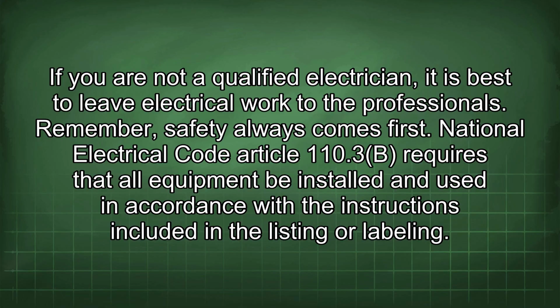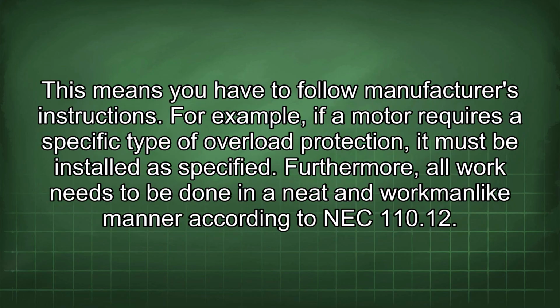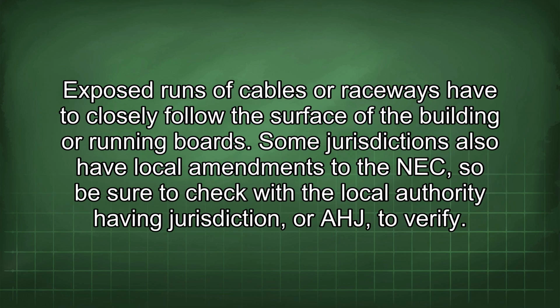National Electrical Code Article 110.3(B) requires that all equipment be installed and used in accordance with the instructions included in the listing or labeling. This means you have to follow manufacturer's instructions. For example, if a motor requires a specific type of overload protection, it must be installed as specified. Furthermore, all work needs to be done in a neat and workmanlike manner according to NEC 110.12. Exposed runs of cables or raceways have to closely follow the surface of the building or running boards.